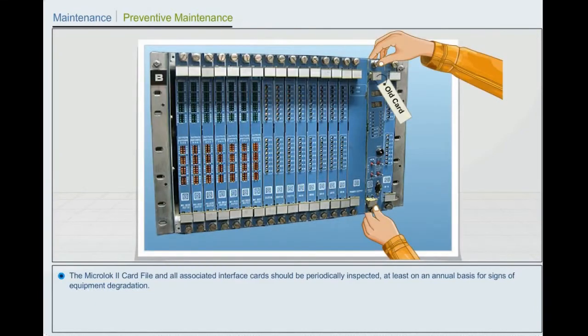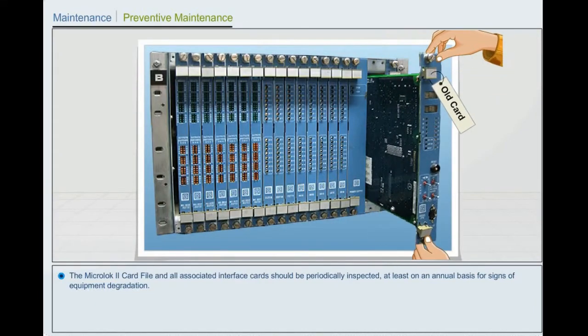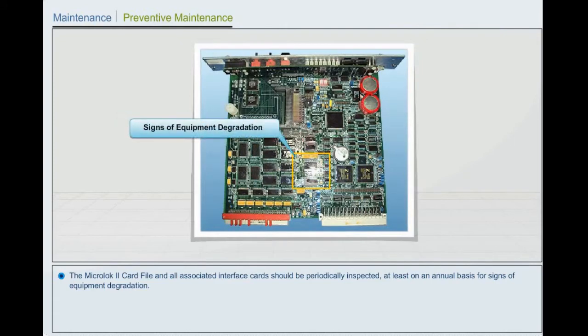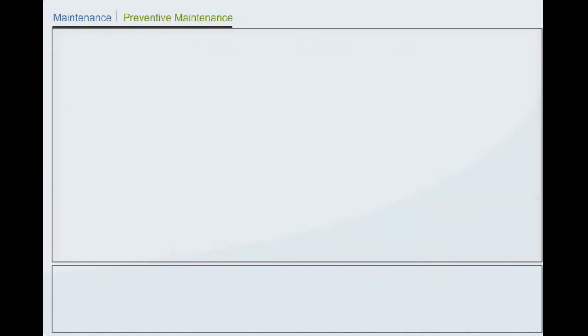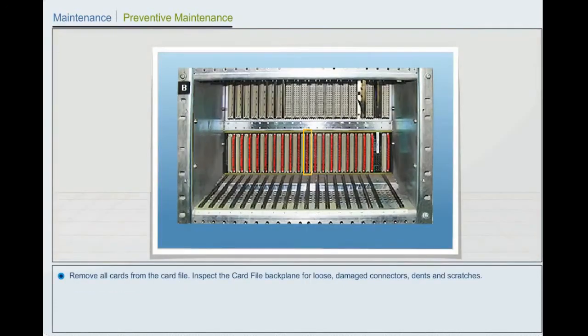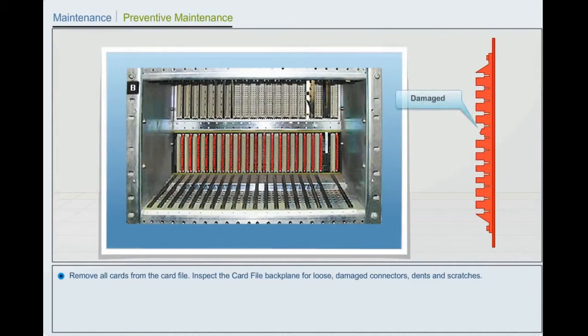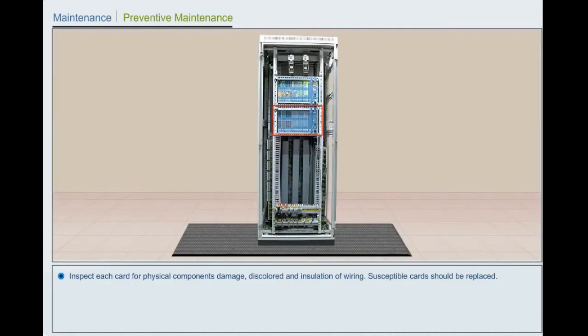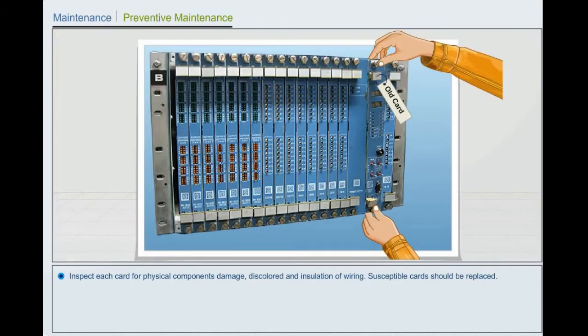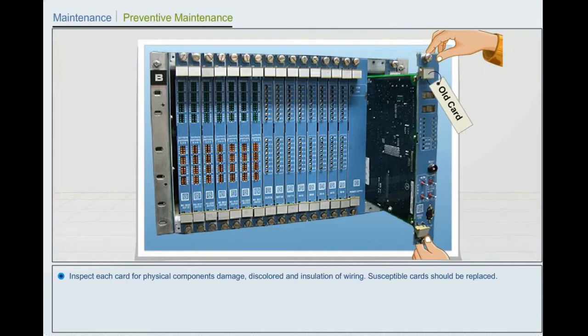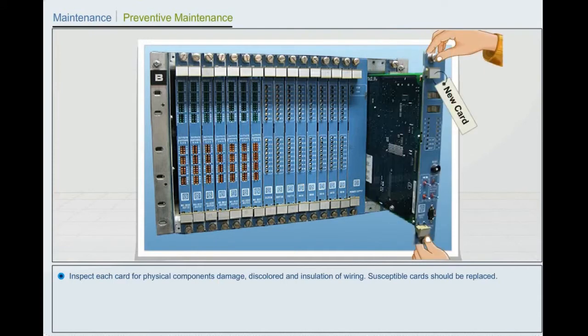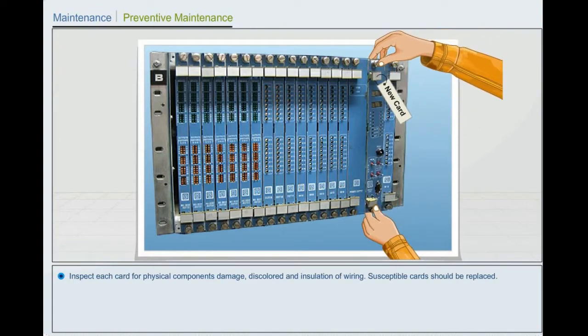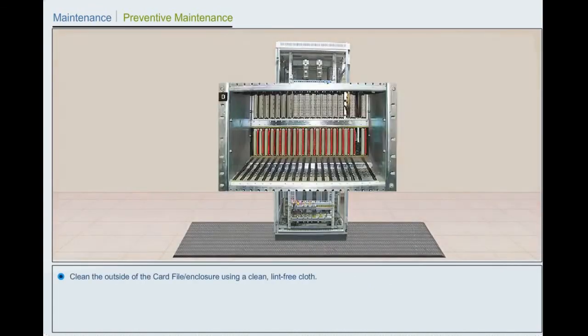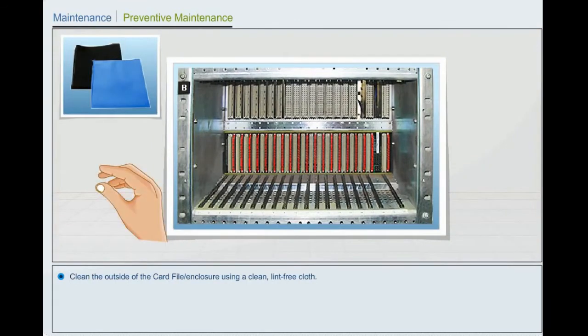The Microlok II card file and all associated interface cards should be periodically inspected at least on an annual basis for signs of equipment degradation. Remove all cards from the card file. Inspect the card file backplane for loose, damaged connectors, dents, and scratches. Inspect each card for physical component damage, discoloration, and insulation of wiring. Susceptible cards should be replaced. Clean the outside of the card file or enclosure using a clean, lint-free cloth.